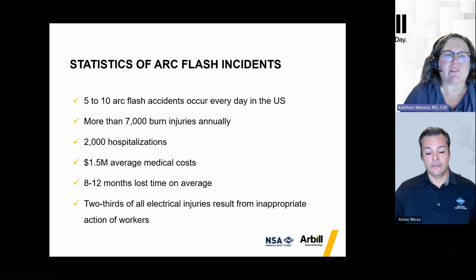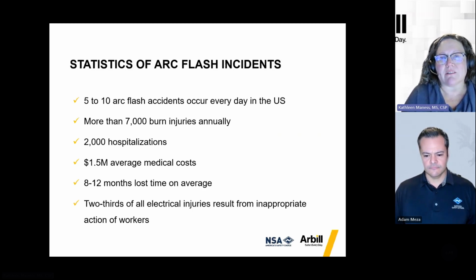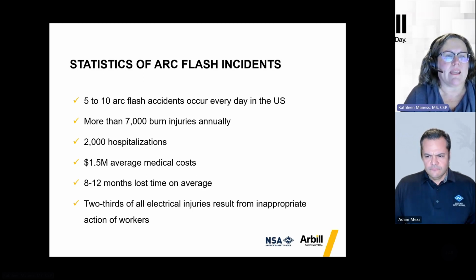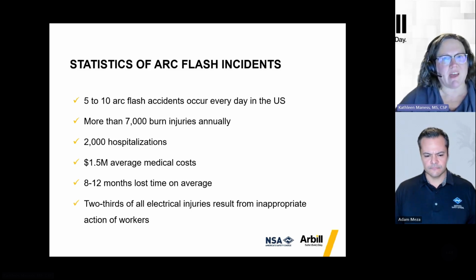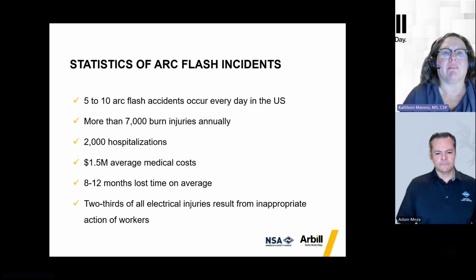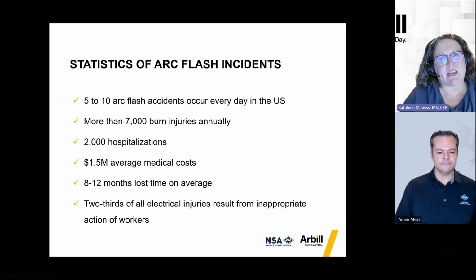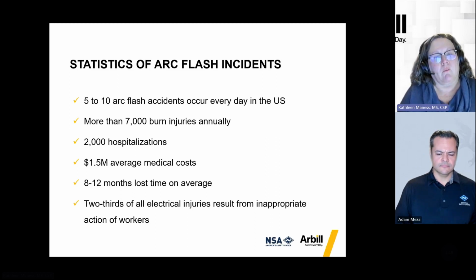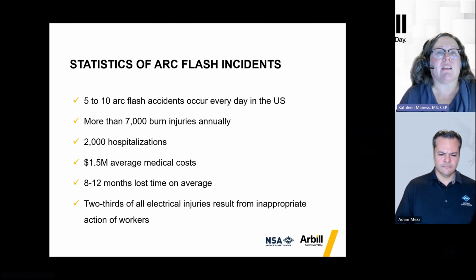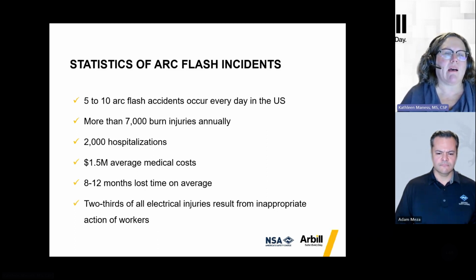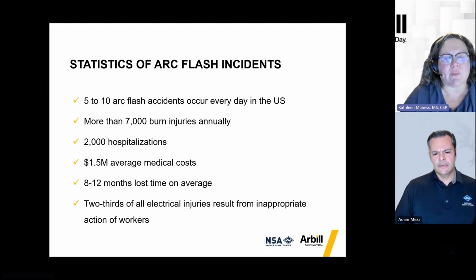Some other statistics around arc flashes: between 5 and 10 occur every day in the United States. Those result in up to 7,000 burns annually, up to 2,000 hospitalizations, and for each incident we can see an average of 1.5 million dollars in medical costs. Again, we have that long road of recovery and rehabilitation associated with these incidents. Even more so, we can see folks involved losing 8 to 12 months of time at work. That's 8 to 12 months where not only is that individual not working, but we need to fill in for them, train somebody, maybe hire some temporary help. So the indirect costs continue to add up with these incidents.